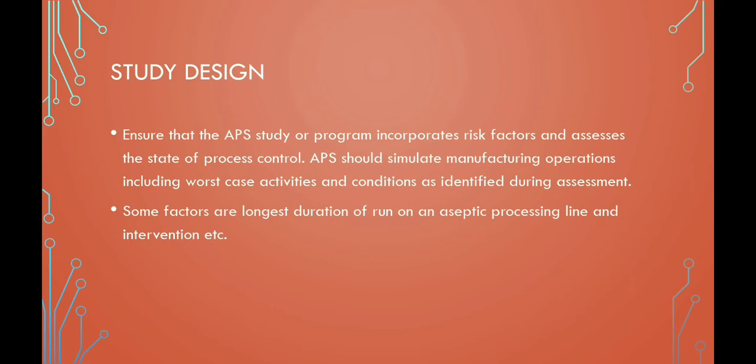For the study design, ensure that the aseptic process simulation program incorporates risk factors and assesses the state of process control. Aseptic process simulation should simulate manufacturing operations including worst-case activities and conditions as identified during risk assessment. Factors to be simulated or evaluated include the filling operation, the longest duration of a run on the aseptic processing line, and various interventions that may be inherent or corrective, such as aseptic assembly or line setup.